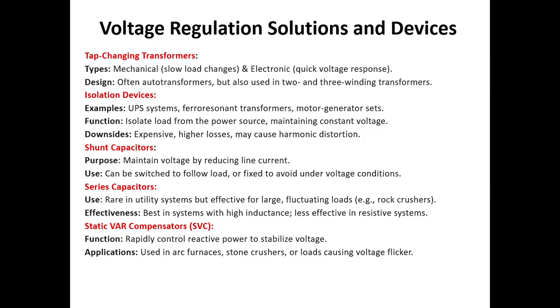Now, voltage regulation solutions and their devices. What are the voltage regulation solutions? The first one is tap changing transformers. That means either we go for the off-load type, or otherwise we go for the electronic, automated one, that is OLTCs. Now, what types of designs are there? Often it is one type of auto transformer, but usually also in 2 or 3 winding transformers.